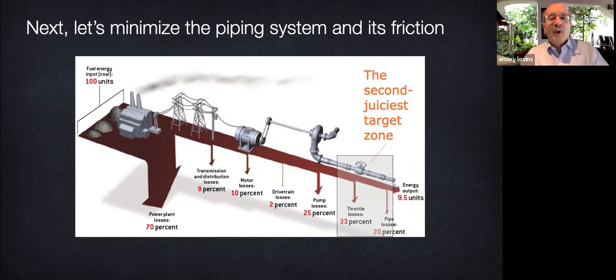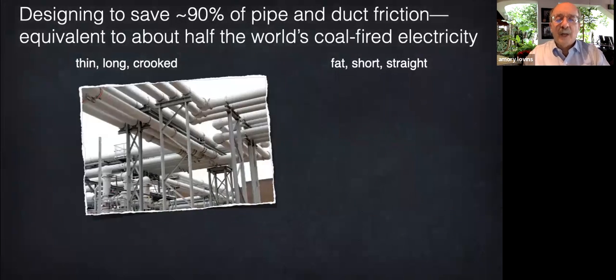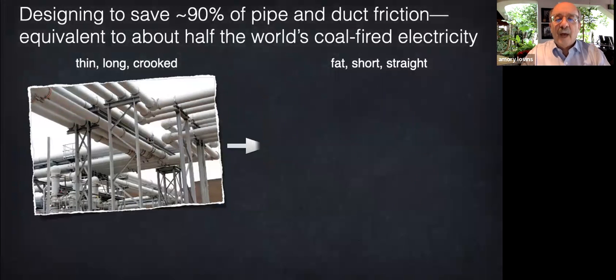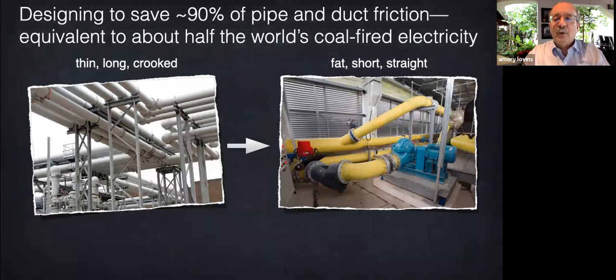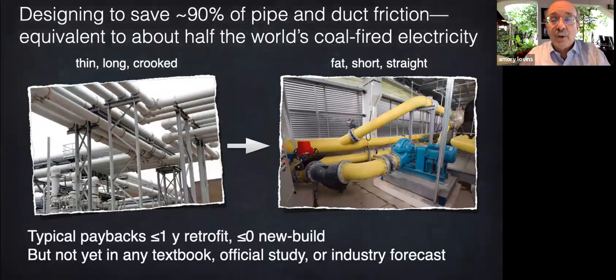Next, and omitted by nearly all practitioners for about the past century, we can deliver the minimum required flow with 80 to 90% less friction by properly designing the piping system. If pipes are made not skinny, long, and crooked, but fat, short, and straight, friction drops by 80 to 90%. If this were done worldwide, such proper pipe and duct design could save roughly a fifth of the world's electricity, or half the world's coal-fired electricity, with extremely juicy returns.